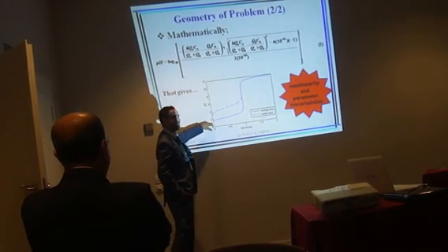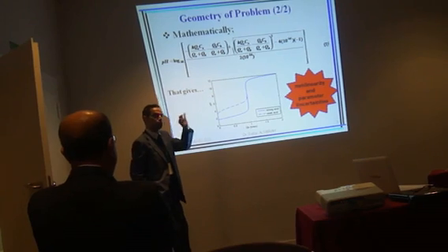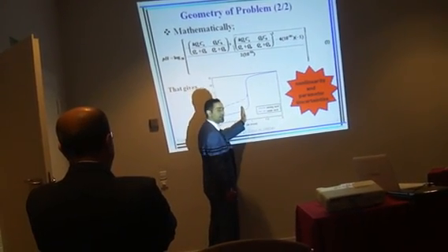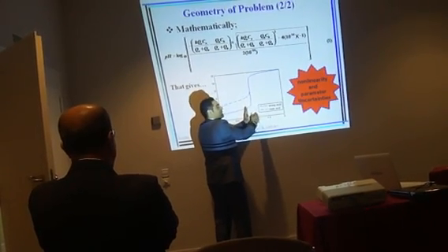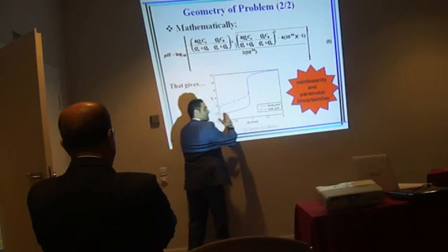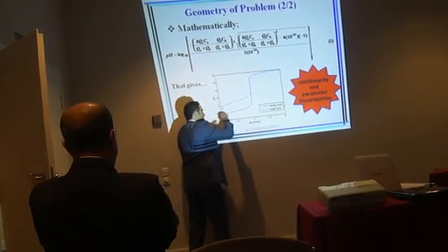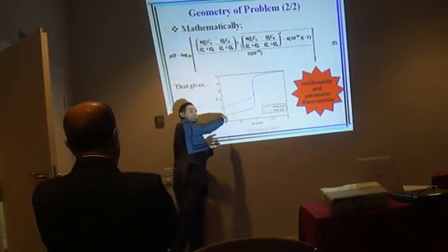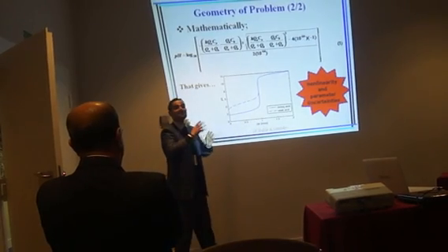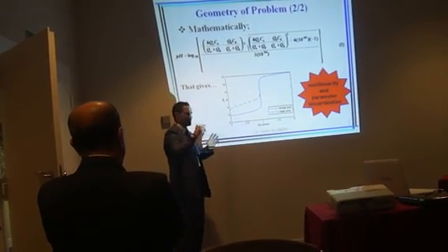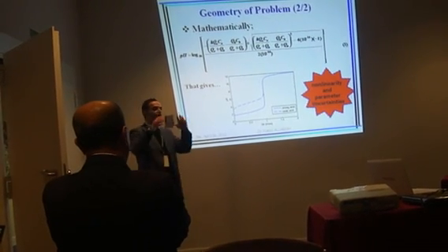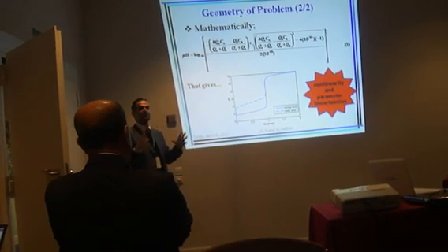If we compare the solid curve and the dashed line, the first note we could conclude from this figure is that when Q base changes from approximately 0.9 liters per minute to 1.1 liters per minute, we have a very fast variation of pH. It means when Q base is less than 0.9, pH increases, but slowly. So it's a linear relationship. But between 0.9 and 1.1, it's extremely nonlinear. This very fast variation could cause the control system to lose its stability. And you know, in control system design, all the interest is to enhance stability and improve the response of closed-loop systems.